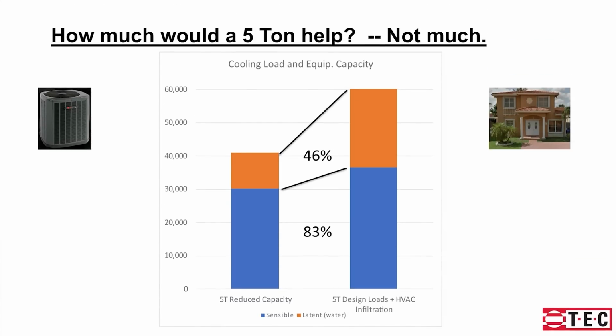Okay. You're chasing your tail. So now we got only slightly better. Before, we were covering 41% of the latent load. Now we're covering 46%. Is that going to make a big difference? No, it's still going to be crazy humid. And instead of covering 74% of the sensible load, now we're covering 83%. So maybe instead of slipping 8 degrees, you're going to slip 6.